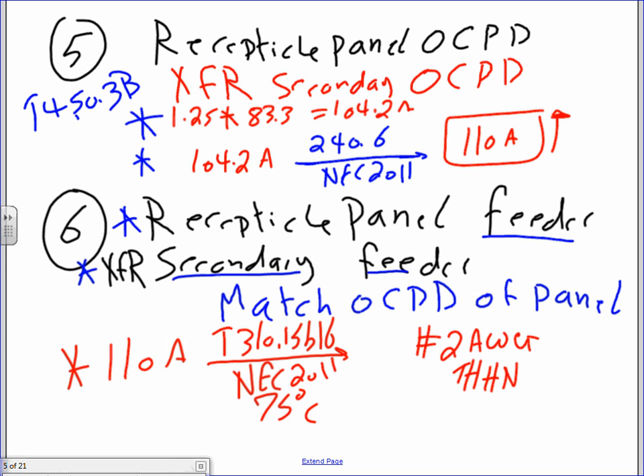and insulation THHN. And how many conductors? Anybody can tell me how many? You need 3 at least for a 3-phase. Do you need a neutral? Yes. So you need 4 conductors, full neutral, 4 conductors, number 2. Up to 225 amp panel, it's a good idea to have a full neutral. Did you guys hear me? Higher than 200 to 225 amp panel, you start cutting the neutral by 70%. Remember when we sized that, over 200 you cut it by 70%.